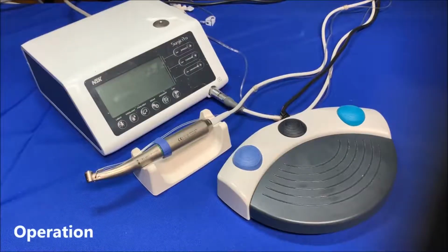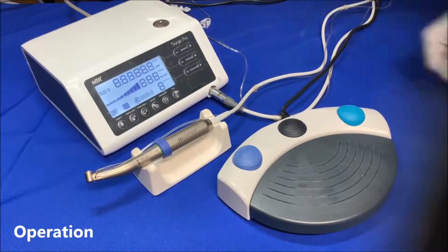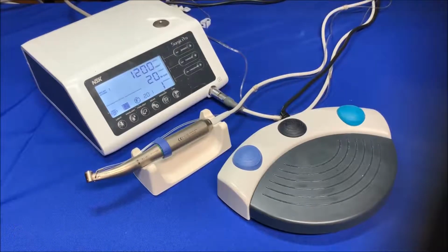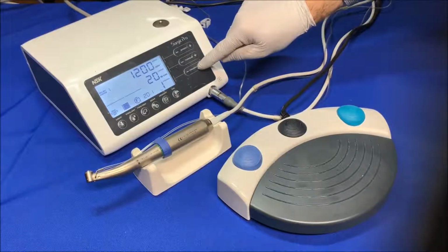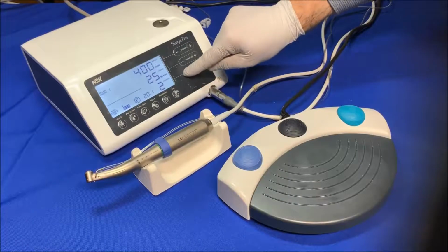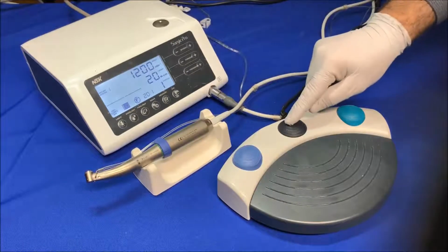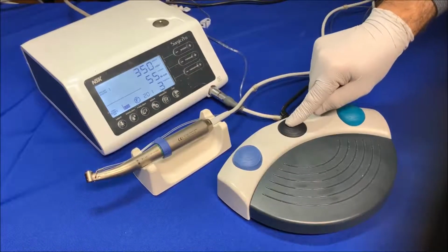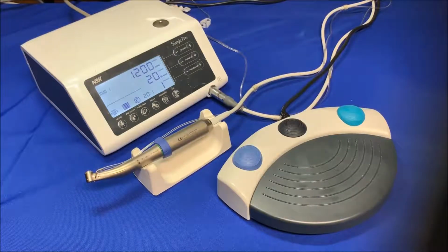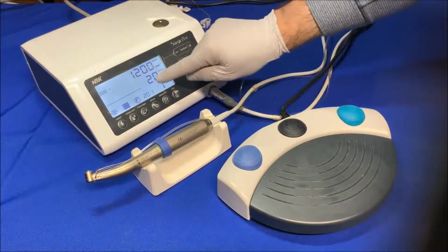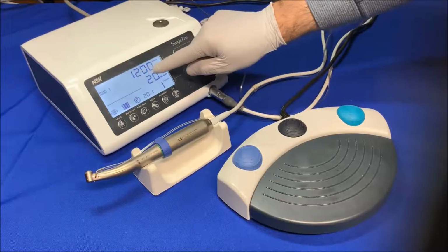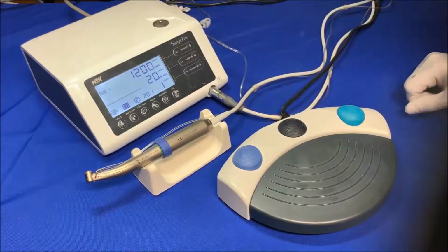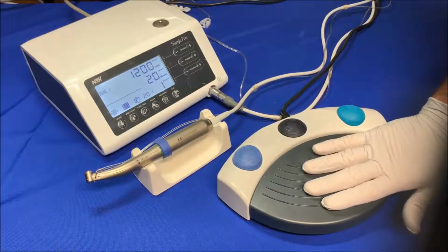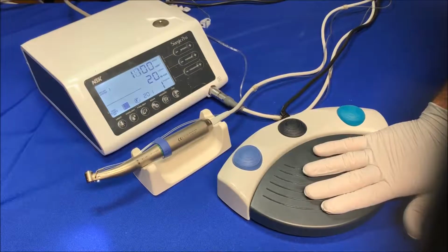Let's talk about the operation. Turn on the power. Select the desired preset program number by pressing the plus or minus on the control panel or the black button on the foot control. Verify the program details as far as torque and speed. Step on the speed control pedal in the middle of the foot control and the micromotor and the pump will start to run.